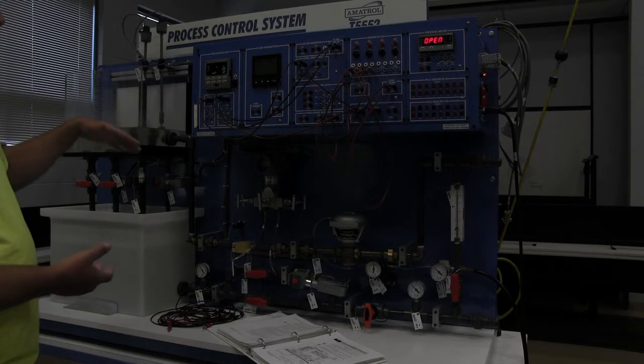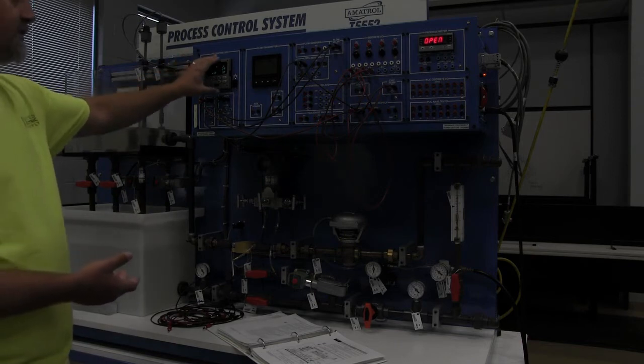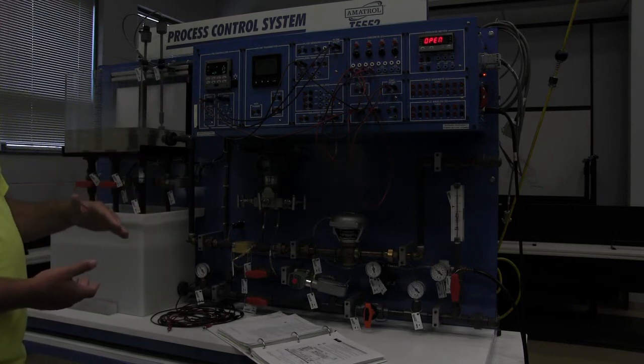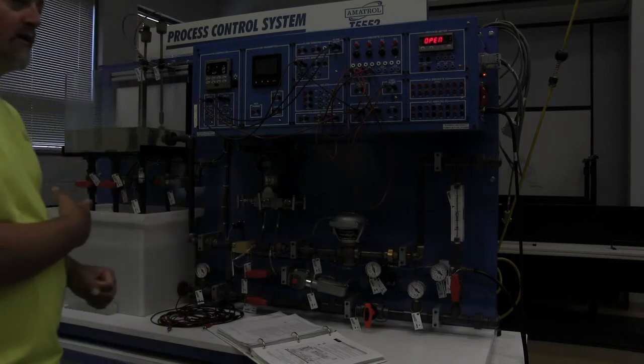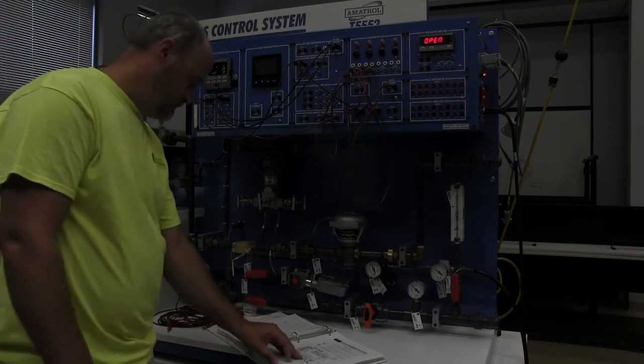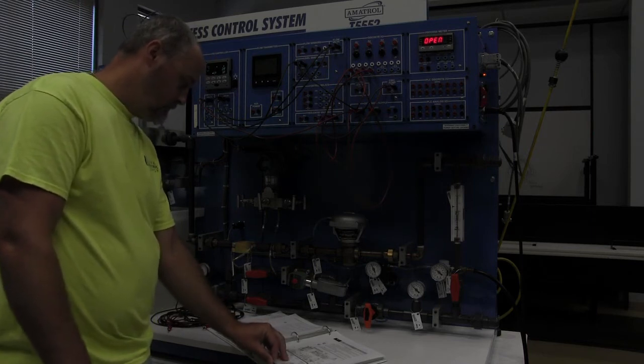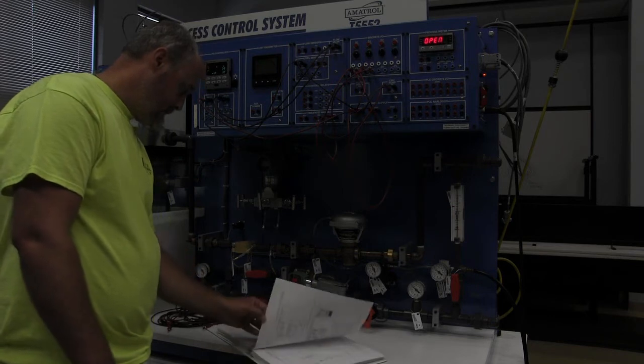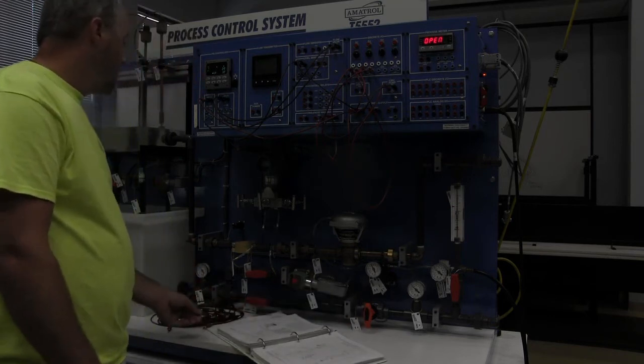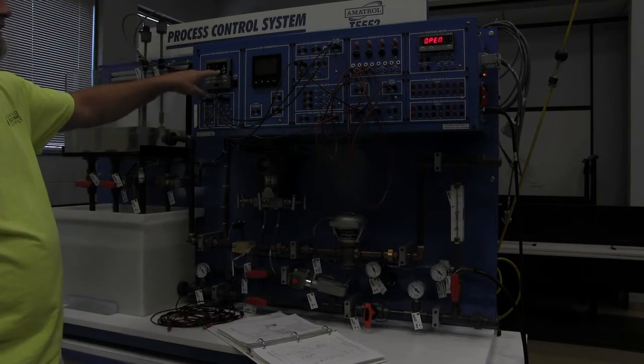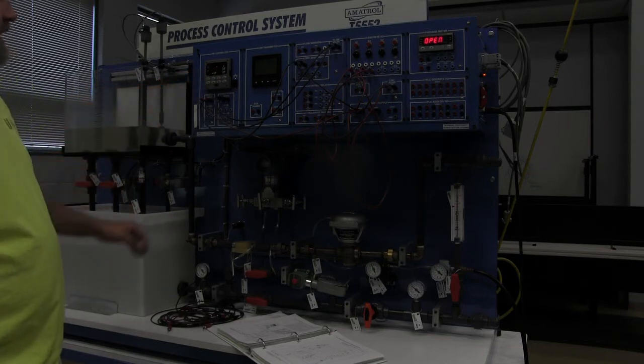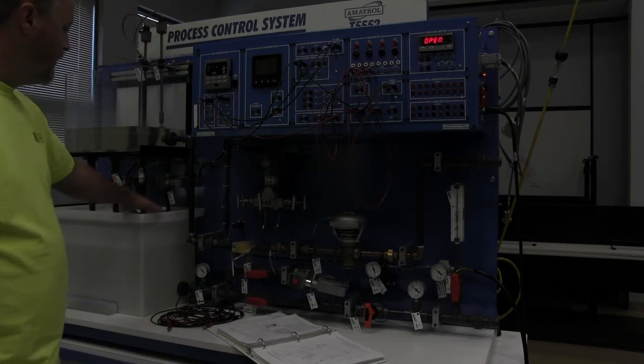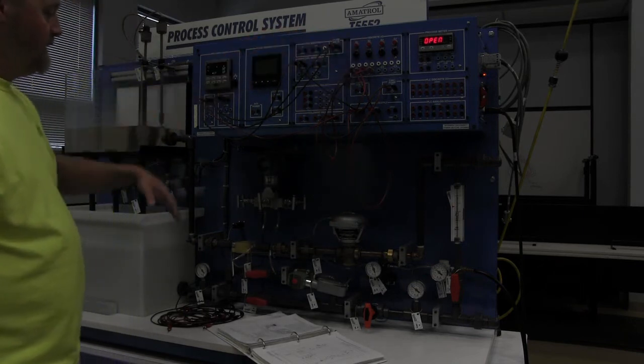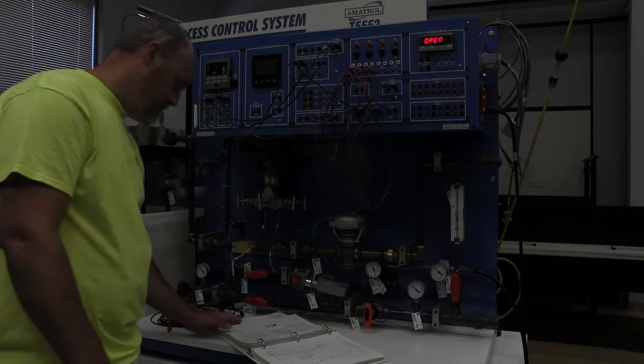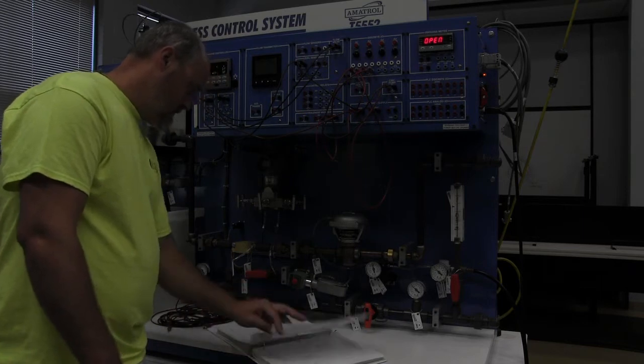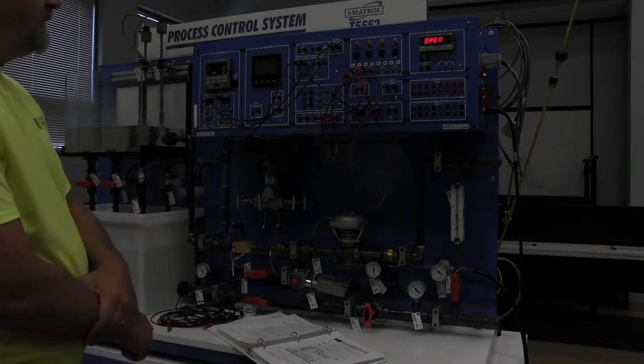So earlier we did it off the floats trying to keep a level in the tank. Now we're doing it based off of a controller and a level transmitter. As it gets below 3, this valve is going to open up and try to put more water in to maintain that set point. And now it's coming back up. It got down to a 2.7. Now it's coming up to a 2.9. Now the controller is going to tell this valve stop. The level is going to drain a little bit based off of the solenoid valve still being on, and then it's going to open that air valve to allow more to come in. And that's just maintaining a level in a tank.